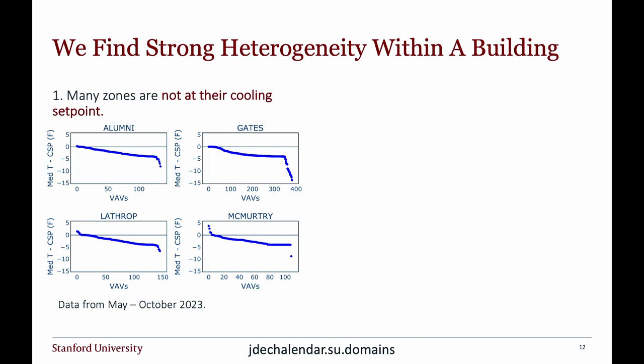The x-axis here is just zones. What this is showing is that most zones in these buildings are, what I would say, overcooled - they're colder than they could be. This is data from May to October of 2023, so the temperature outside is hotter than the set point most times in the periods I'm averaging, taking the median over here.